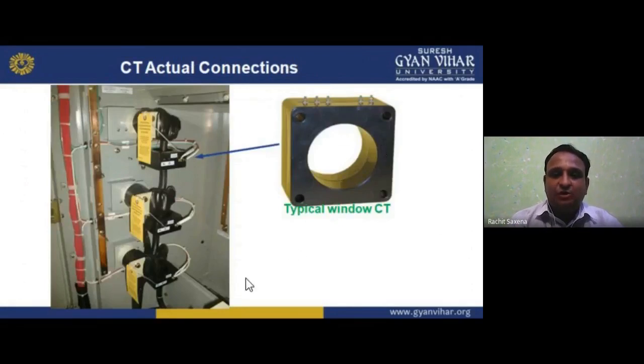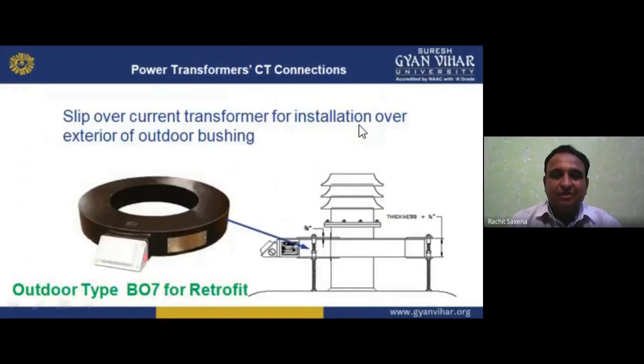Then the typical window CT, we have the CT actual connections. Now see here, it is connected in the board, we can say the electric board and the supply. We have the system, that is the CT actual connections. The typical window CT we are having has H1 and X1, meaning primary and secondary. Now the power transformer CT connection. So we have the power transformer, and we connect the CT at this point for the current measurement.